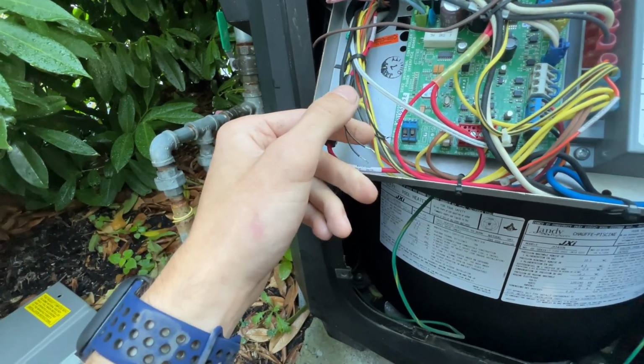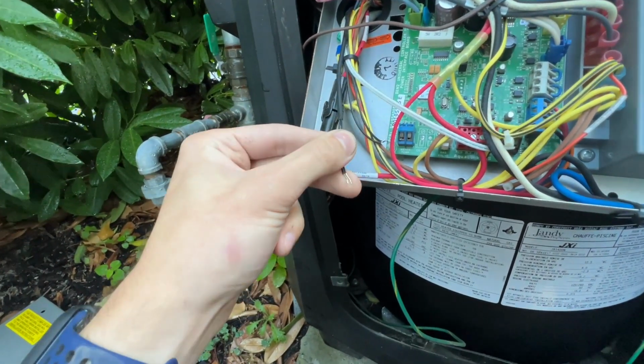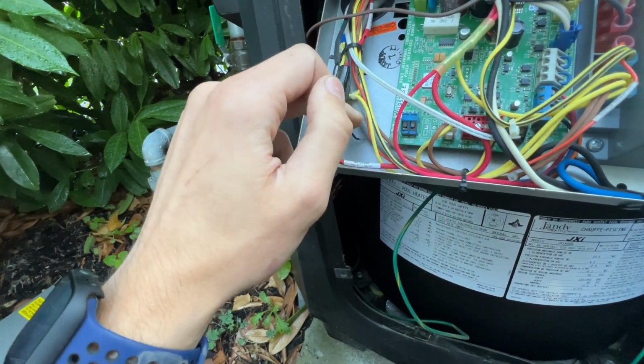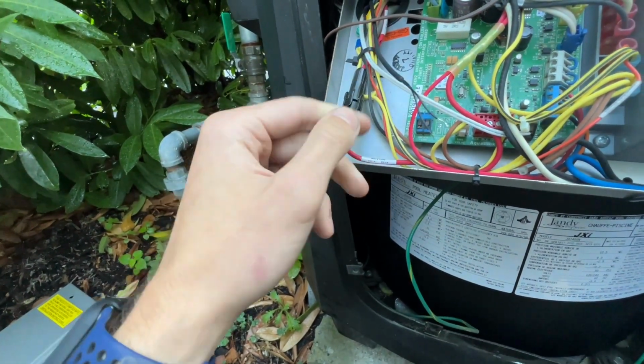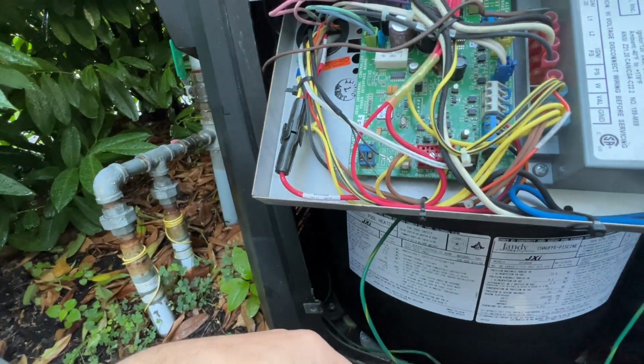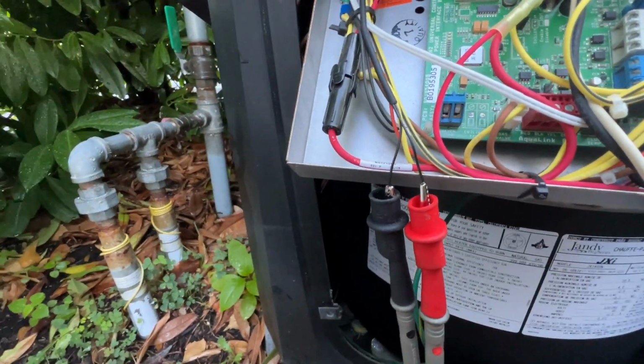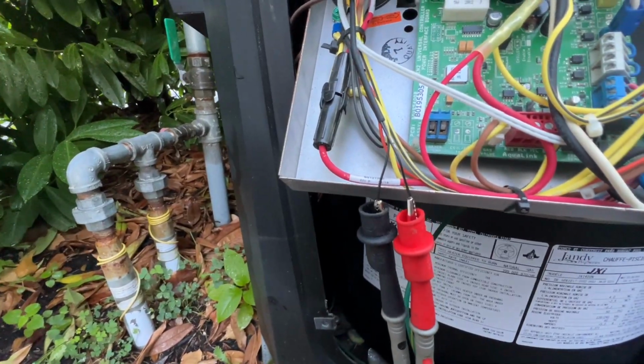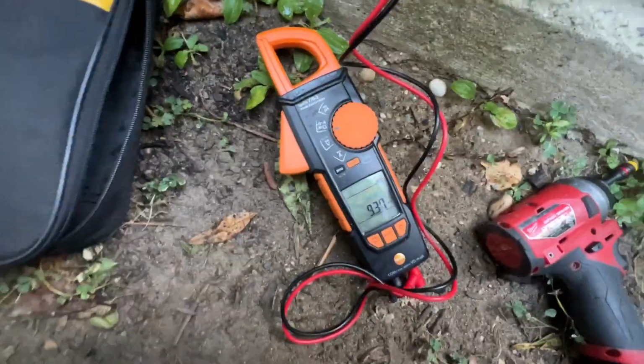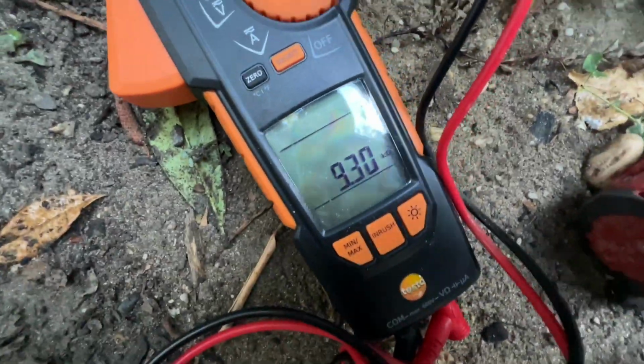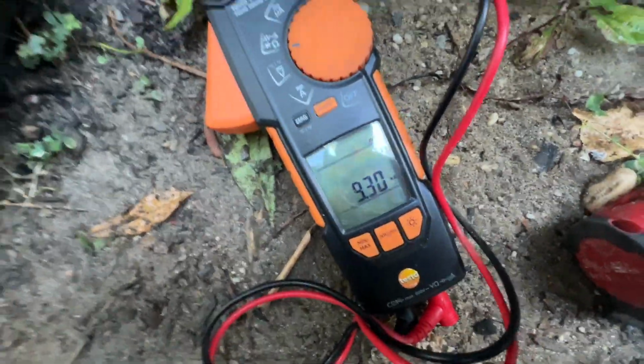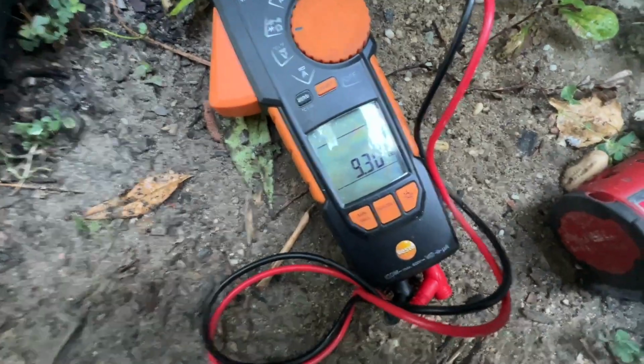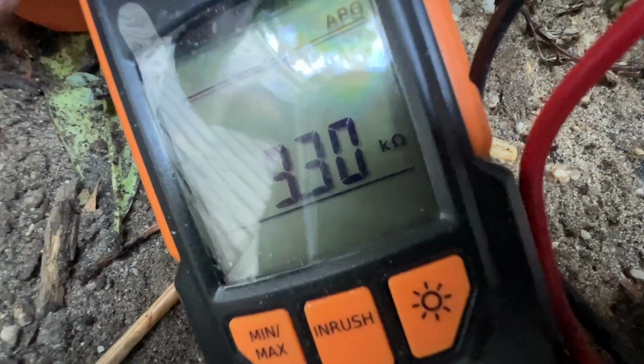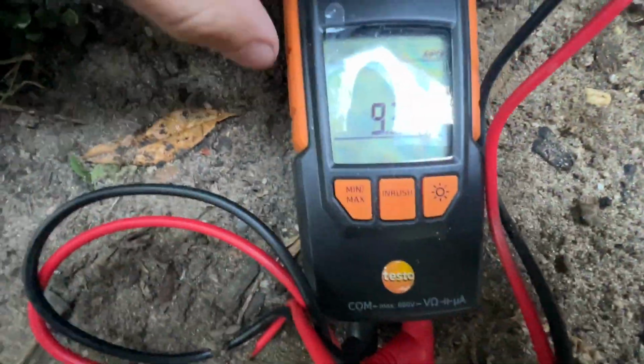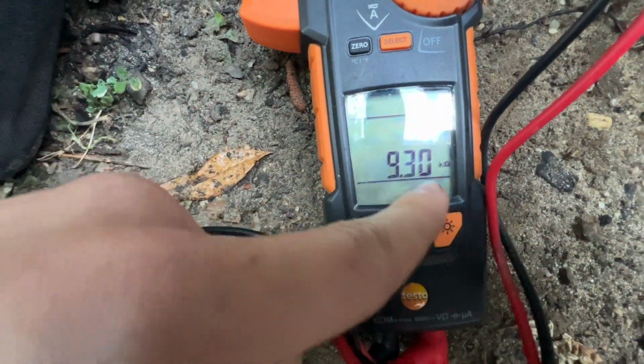So I'll test that and see what it reads. You can see we also have an old sensor right here, but I'll test it and see what happens. Okay, I have my test leads on the temperature sensor, and you can see we're reading 9.3, and that's right about where it needs to be. That's kiloohms, not just regular ohms, so that's about 9,300 ohms.